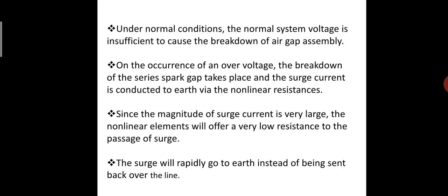Since the magnitude of surge current is very large, the non-linear elements will offer a very low resistance to the passage of the surge. The surge will rapidly go to earth, instead of being sent back over the line.